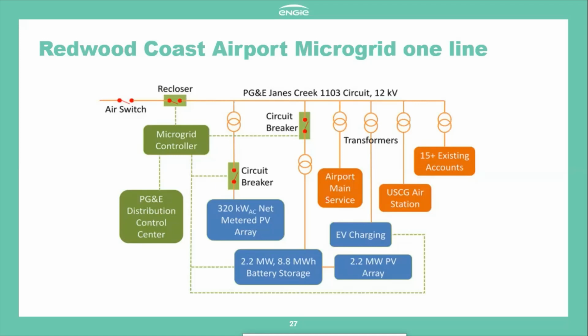I didn't realize they could do curtailment as well on equipment. Is that common, or is that a special feature you have to look for? That's a newer, more sophisticated microgrid controller. Most microgrid controllers will just balance whatever is coming in between the two generators, and send it to whatever is being consumed in the building or the critical load panel.